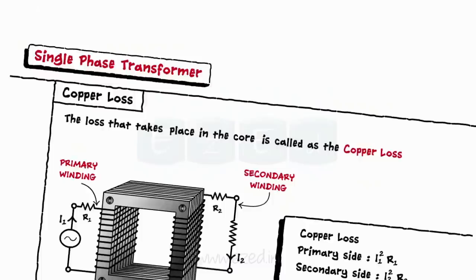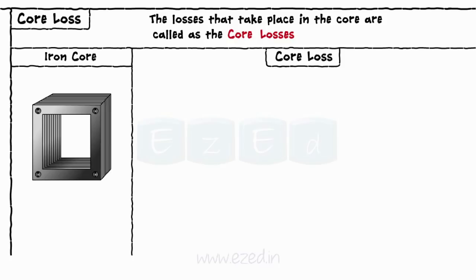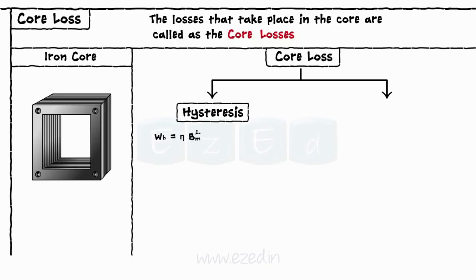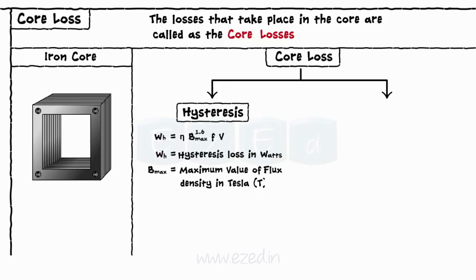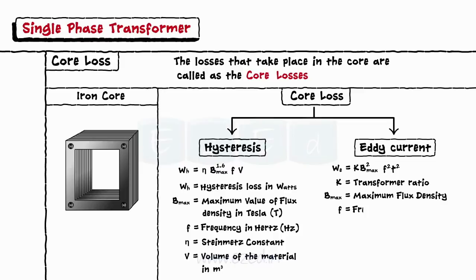The losses that take place in the core are called core losses or iron losses, as the core is made up of iron. These losses are of two types. Hysteresis losses given by WH = η × Bmax^1.6 × f × V, where WH is the hysteresis loss in watts, Bmax is the maximum value of flux density in Tesla, f is the frequency in Hertz, η is the Steinmetz constant, and V is the volume of the material in cubic meters. Eddy current losses are given as WE = K × Bmax² × f² × t², where K is the transformer ratio, Bmax is the maximum flux density, f is the frequency in Hertz, and t is the thickness of the lamination.